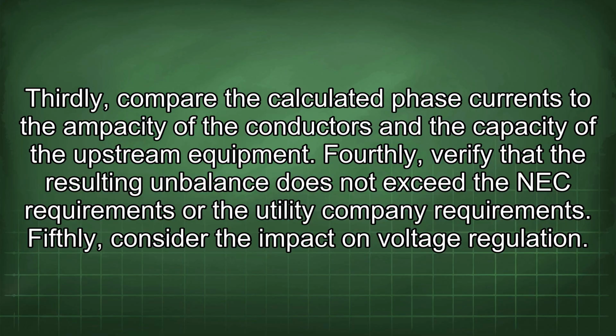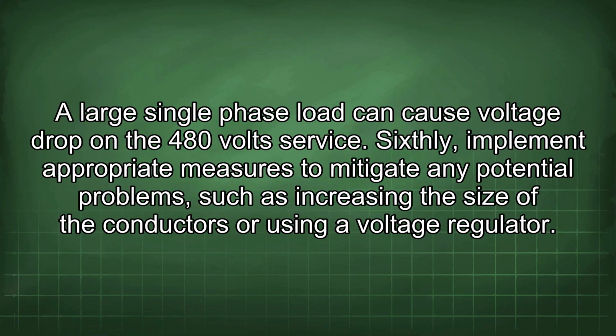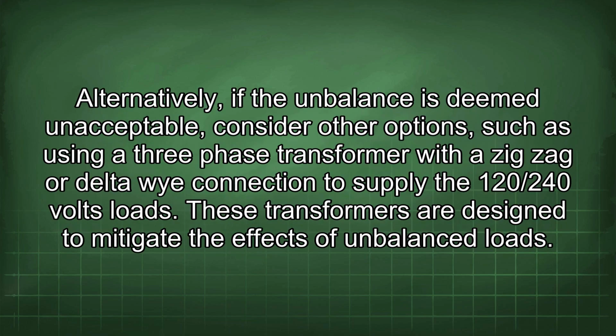Fifthly, consider the impact on voltage regulation. A large single-phase load can cause voltage drop in the 480-volt service. Sixthly, implement appropriate measures to mitigate any potential problems, such as increasing the size of the conductors or using a voltage regulator.